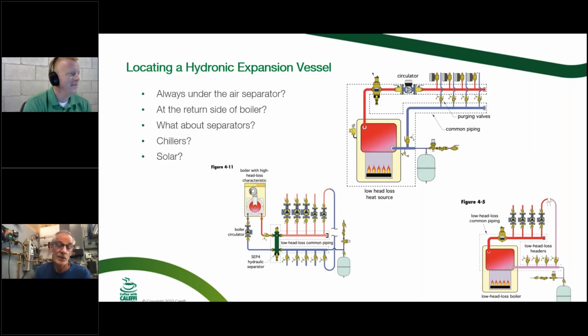So here's to Cody's point and to the answers that are coming in: classic examples of how you could put the expansion tank, number one, on the cooler fluid side of your system, and also not under the air separator on top, because it's going to leak into the boiler someday if it was hanging under those air separators in those two pictures. They're all going to leak. That's just one given about expansion tanks: they're going to fail. They're either going to rust through, the diaphragm's going to rupture, or the Schrader valve is going to fail. They're all going to leak at some point in their lifetime, I guess you could say.